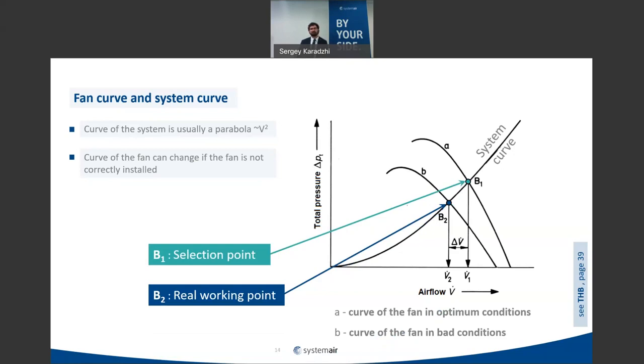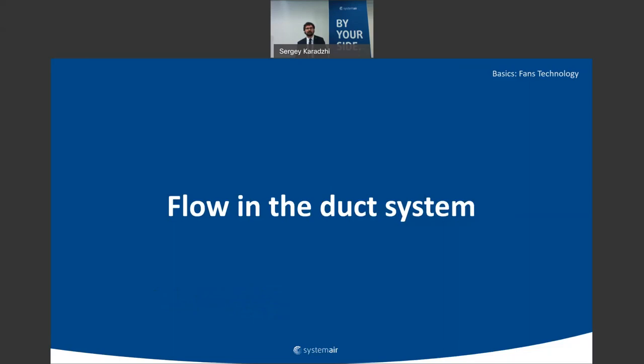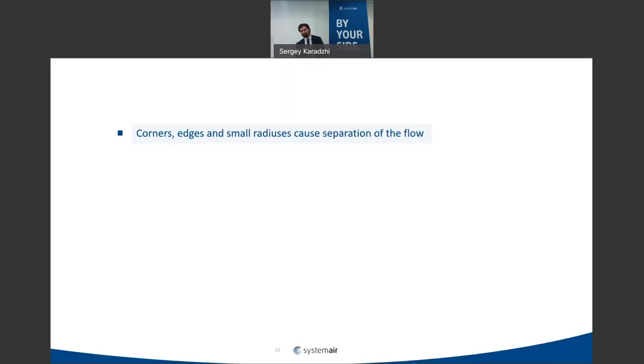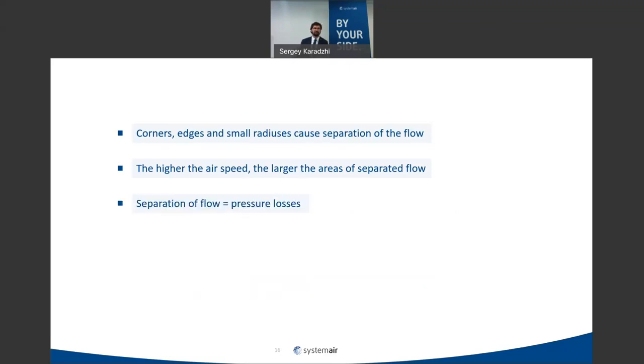Flow in the duct system: the main things that cause losses are corners, edges, and small radii. These can be found in technical handbooks. Higher velocity means larger areas of flow separation and therefore higher pressure losses — losses are proportional to dynamic pressure at that location through a loss coefficient. Any separations entering the fan cause not only pressure losses but also a change in the fan curve.